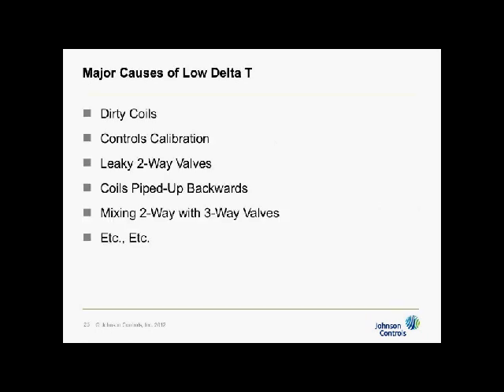Now let's see what causes that to happen. First, we could have dirty coils, and I'll go in a little more detail on that particular one. We could have our controls out of calibration. We could have leaky two-way valves. Coils could be piped up backwards. We could have mixing of 2- and 3-way valves in the same system. There's probably 10 different causes of low delta T, but these 5 are the most prevalent and usually the largest, of which the 5, dirty coils, is probably the worst offender.